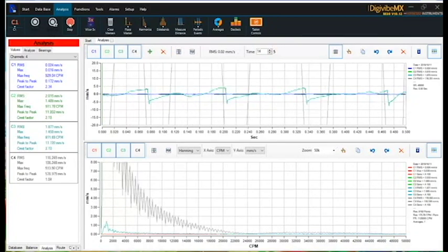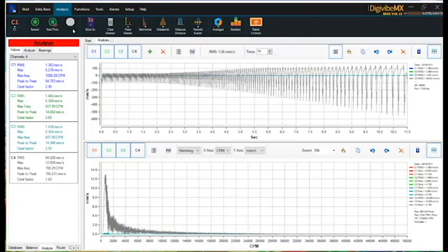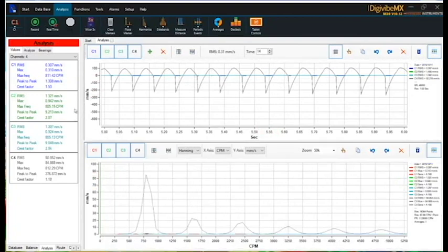And just wait until either the rotor reaches the speed you need or the motor stops. In this case, the motor is stopping. So let's say I want to balance at 1200 RPM. Try to select the same number of seconds always.